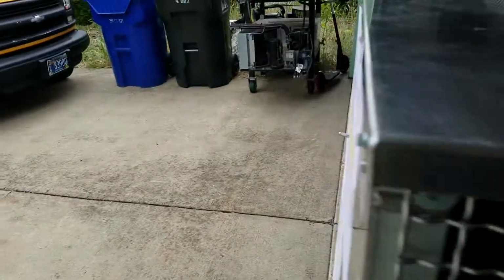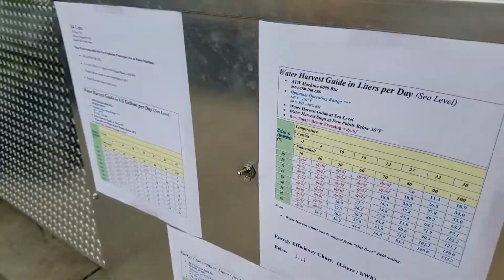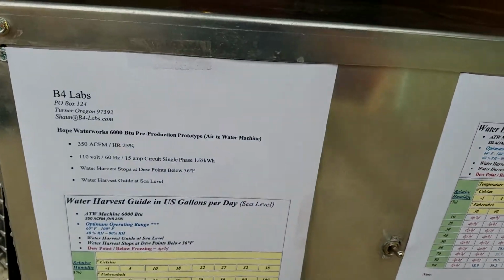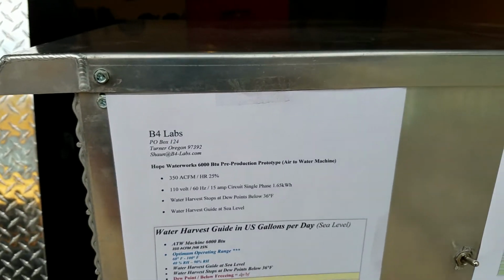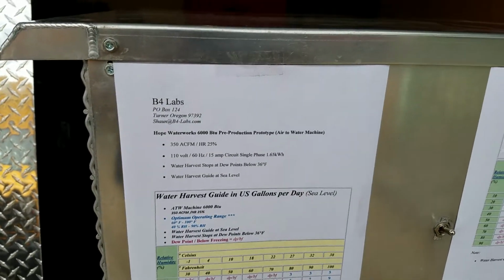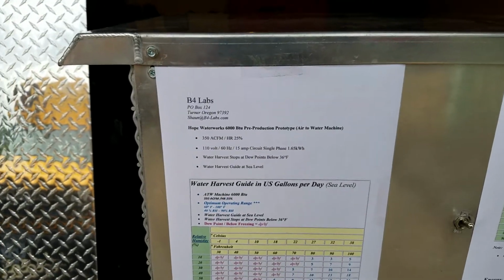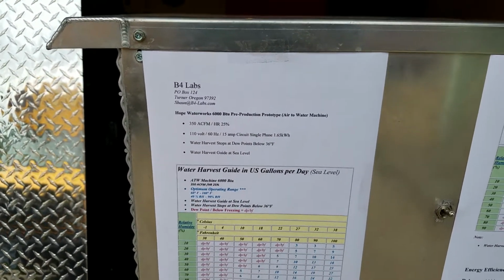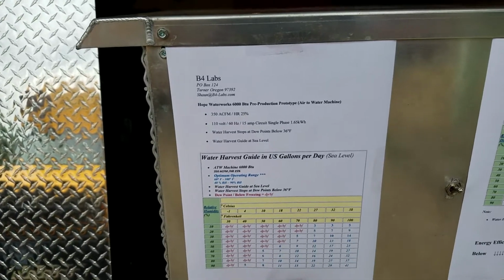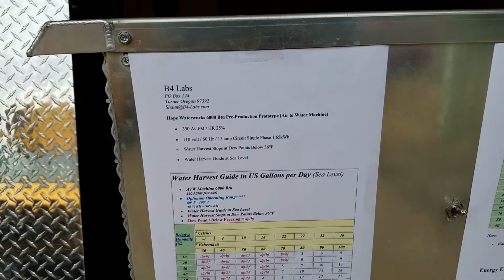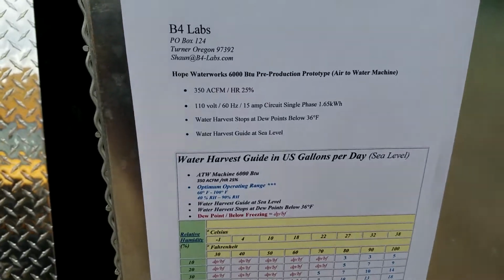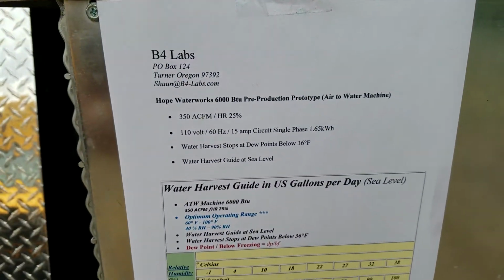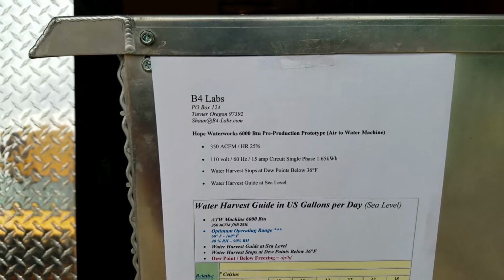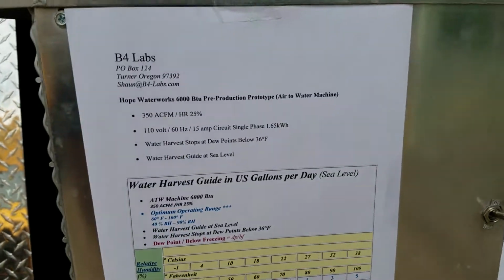So we're going to walk around to the other side of the machine, where I have taped some of the charts. Now the charts are based on lots of field testing, but it's measured in grains per pound in the airstream going through the machine. So we actually weigh the air going into the machine and the air exiting the machine, and we get the weight of the water generated. So the charts are extremely accurate because they measure the amount of water being extracted in water weight.